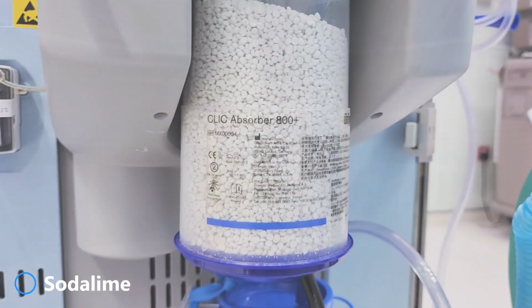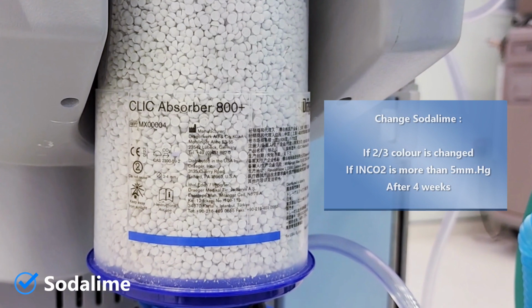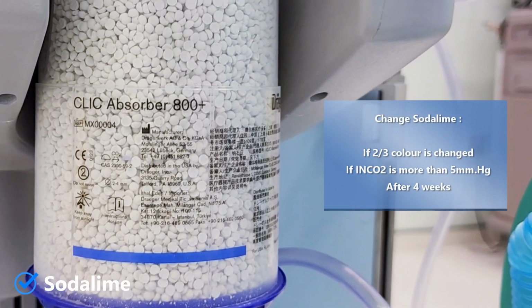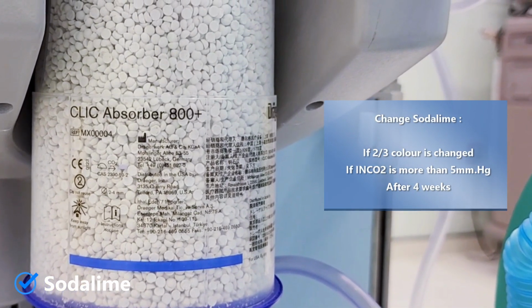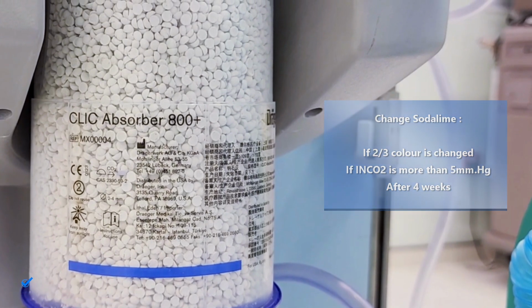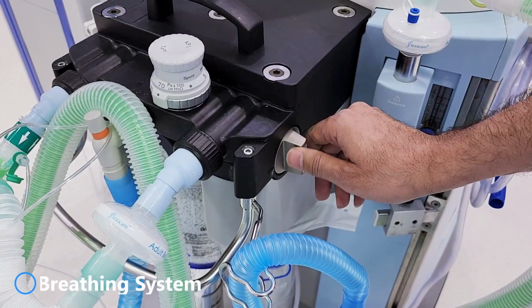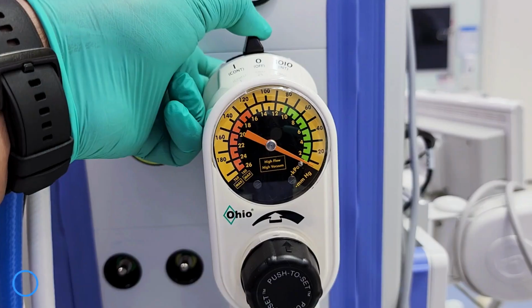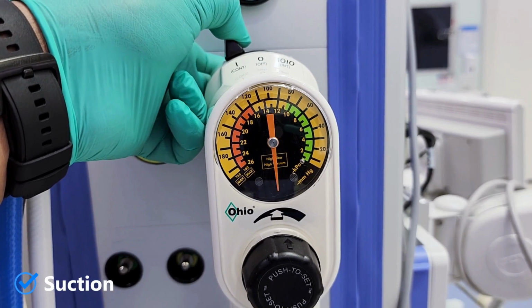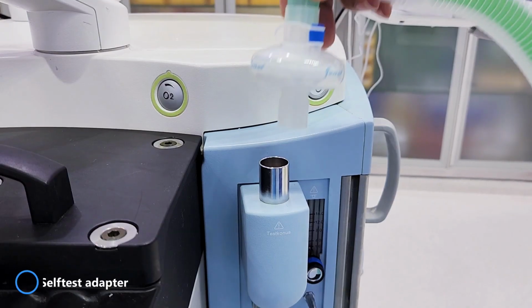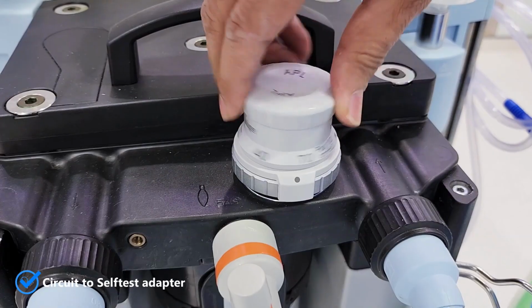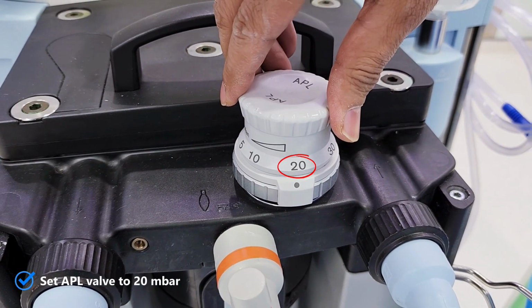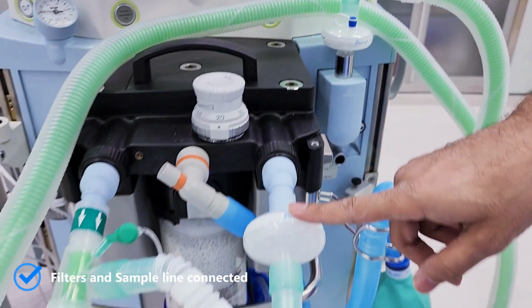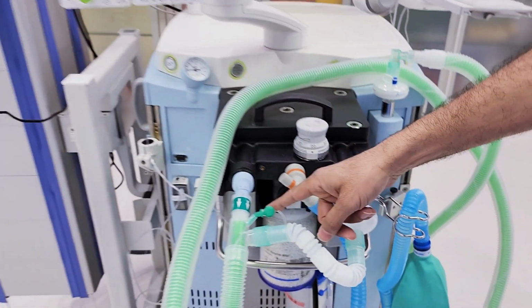The soda lime has to be changed if 2/3 of the color has changed, or if inspiratory CO2 is more than 5 mm of mercury, or after being used for more than 4 weeks. Make sure the breathing system is locked. Make sure the suction is working. Place Y-piece into the self-test adapter. Set APL valve to 20 millibar. And attach HME filter and CO2 sample line.